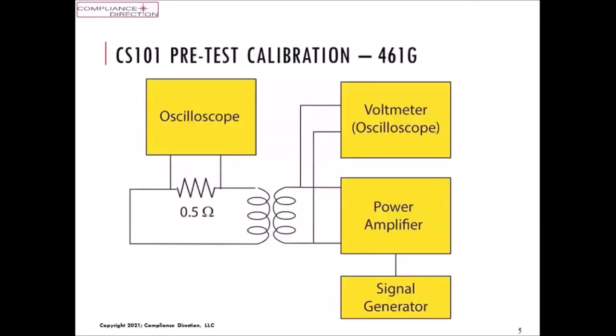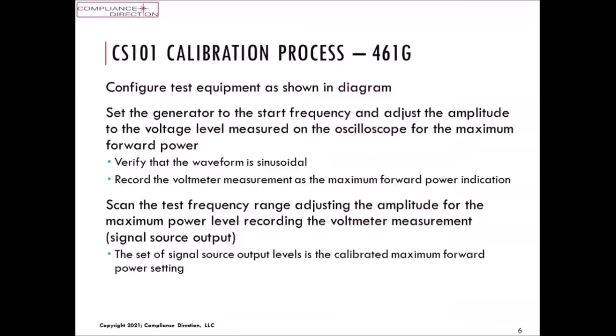So calibration in 461G is here, showing that we develop a power coupled into the circuit. That coupling transformer has a 2 ohm source and a half ohm load impedance secondary. So we're matching the impedance for the half ohm. Now, that's where we adjust to the voltage that we saw measured with the oscilloscope and record what the settings were, what the voltmeter output of the power amplifier or the signal generator was.